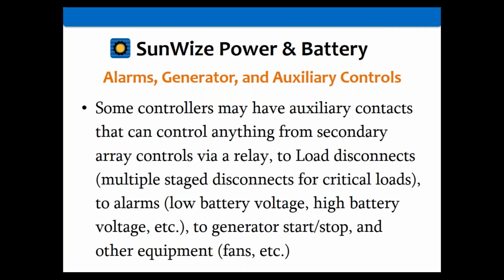You could dial into or connect to, say, the relay driver and tell it you want the generator to start and stop, or turn some fans on or off, all kinds of things. You might also want to turn off a load in the wintertime, say there's less power from the solar array, so you can't support that load anymore, and you shut it off for the season.